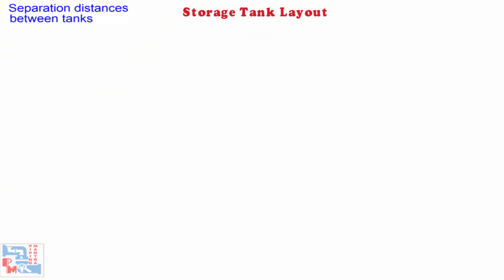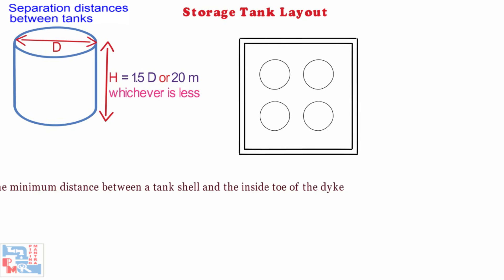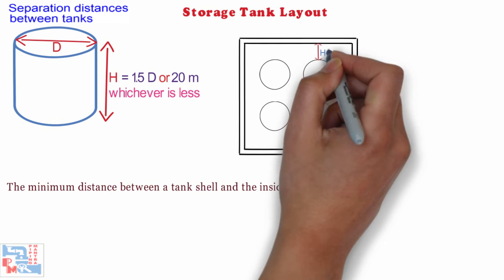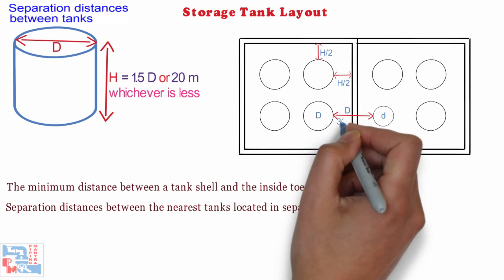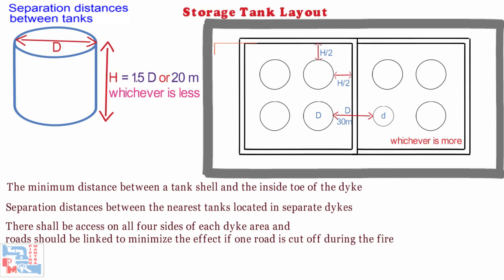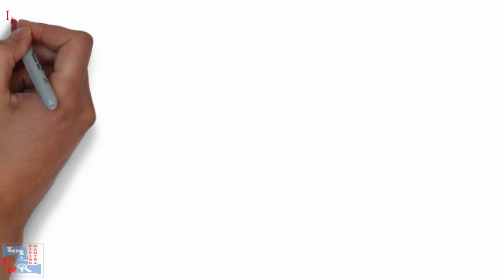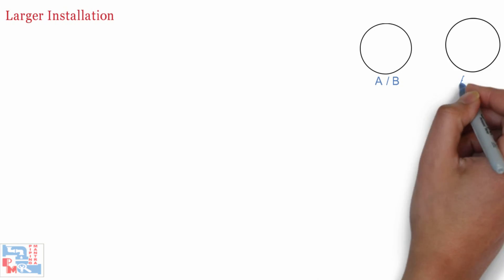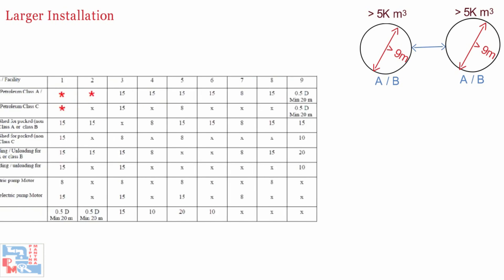Now let's talk about separation distances between tanks. The tank height shall not exceed one and a half times the diameter of the tank or 20 meters, whichever is less. The minimum distance between the tank shell and the inside toe of the dike wall shall not be less than half the height of the tank. Separation distances between the nearest tanks located in separate dikes shall not be less than the diameter of the larger of the two tanks or 30 meters, whichever is more. There shall be access on all four sides of each dike area and roads should be linked to minimize the effect if one road is cut off during fire. For larger installations where total storage capacity for Class A and B petroleum is more than 5,000 cubic meters or the tank diameter exceeds 9 meters, minimum separation distances shall be specified in the relevant tables.